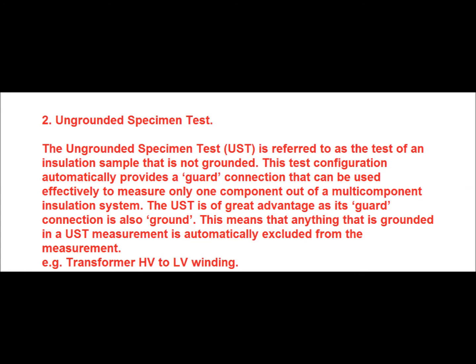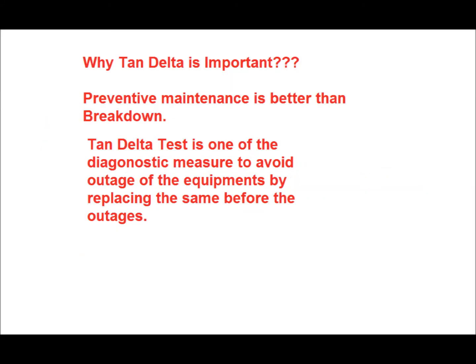For example, the transformer HV to LV winding insulation is measured in UST mode. It is always said that preventive maintenance is better than breakdown. In case of breakdown there is an outage, but in case of preventive maintenance we can change the equipment with a planned shutdown. Over time, the insulation of equipment deteriorates due to the existence of voids in the insulator. Tan delta test is one of the diagnostic measures to avoid outage of the equipment by replacing it before the outage.